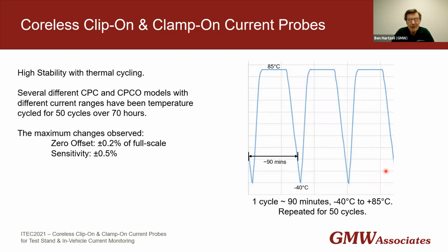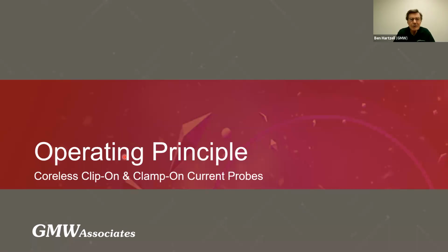Now, to indicate stability with thermal cycling, what we've done is start from room temperature, go to -40, up to plus 85, and total cycle about 90 minutes. And we've cycled that for 50 cycles over 70 hours. And we've done this with several examples of both the ClipOn and the clamp-on probe. And the largest changes we've seen are zero offset, about 0.2% of full scale, and the sensitivity about 0.5% of full scale. So now to go into the operating principle of these sensors.